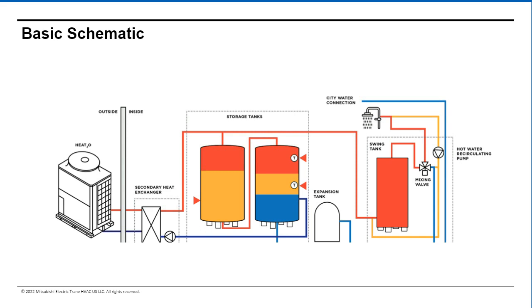From the storage tanks, the domestic hot water goes out to the swing tank, from where it travels out to the three-way mixing valve and out to the plumbing fixtures in the building. The purpose of the swing tank is for loop maintenance inside the building, so that when there's no load, no recent drawdown event, and the hot water heat pump is off, the fixtures in the building can still receive hot water quickly, and the water inside the extensive hydronic piping network does not get stagnant. ASHRAE recommends setting these storage tanks to 140 degrees Fahrenheit to prevent Legionella, and the swing tank at 120 degrees Fahrenheit in order to maximize COP, so that the swing tank's electric element has minimal runtime.